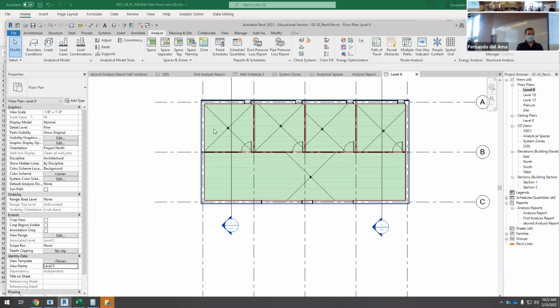If there are a lot of people in one side, we have a cold day, but there is a lot of sunlight entering that room, probably in this room, even in winter, if it's full of people, full of computers, equipment, releasing heat, and we have solar gains, probably at that specific point, on a cold day, we would need the cooling system. Why? Because we are generating a lot of internal loads inside the building.